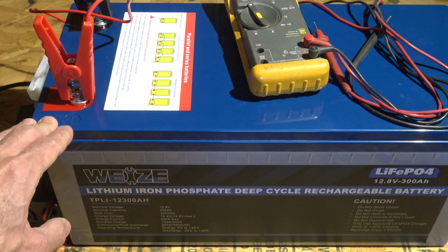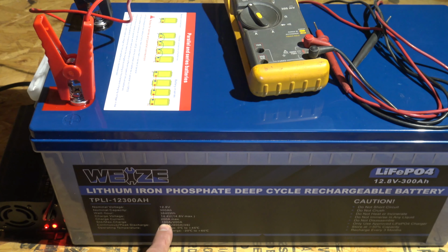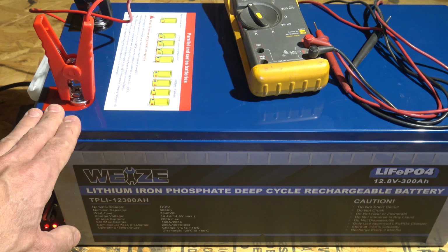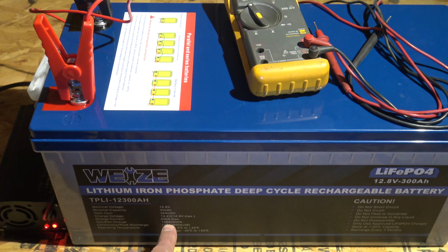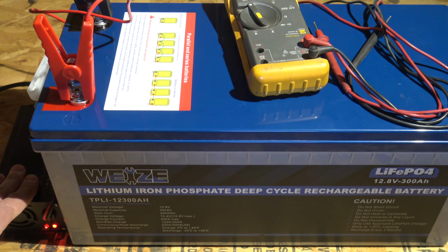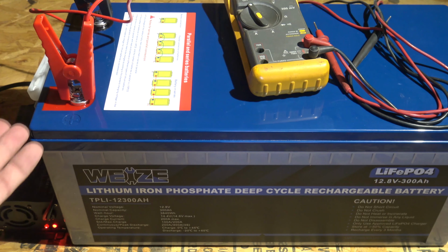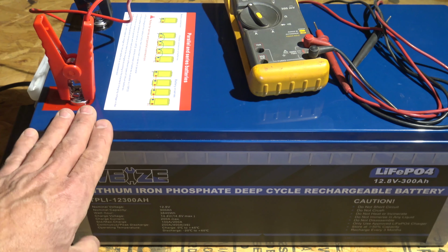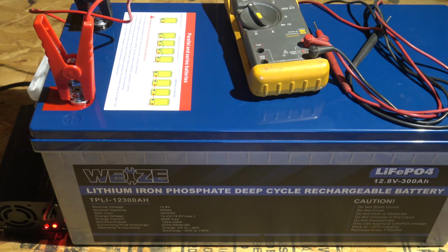Now, standard charging current, it says right here 100 amps. However, I've also read that they recommend 60 amps, a little bit less. But you can go up to a maximum charging current of 200 amps. I'm using a 20 amp charger. I think it does a good job, takes a little bit of time, but I've never had a problem. Slower sometimes is faster, in my opinion - you're not tearing up your equipment. So I go with the 20 amp charger myself. They're cheaper chargers and they work great.